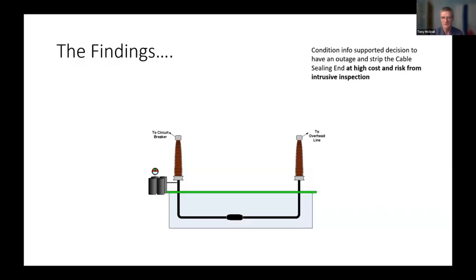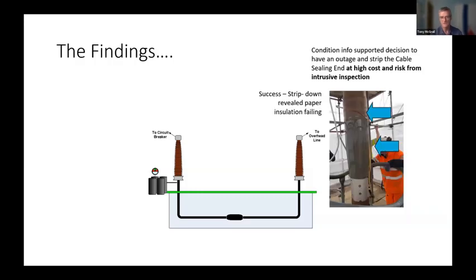Okay, next one, please. What did we do? Strip down the paper, got down to a point where we could find the insulation was actually failing. And you've got arcing marks, you've got burn marks within the cable sealing end. So we know what we have to do to fix it. We're going to take that on, we're going to fix it. Okay, next one, please.